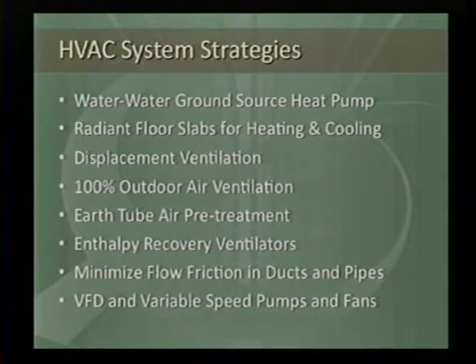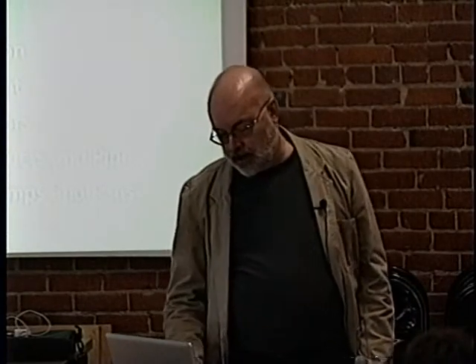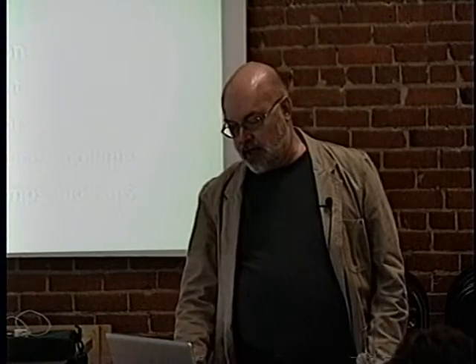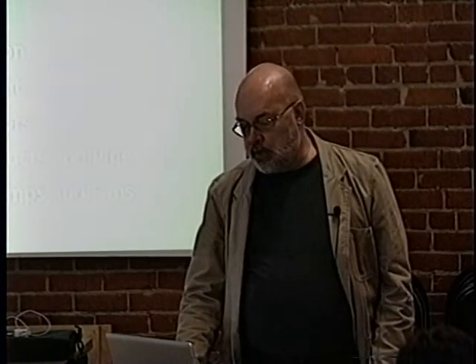We use displacement ventilation. We basically have 100% outdoor air ventilation, and yet our CFM requirement per square foot is about 20% of what a typical building with a VAV system would be. So it's a large reduction in that area. We used earth tubes for air pretreatment. That is, air goes into basically sewer pipe underground and then comes into the air handling unit. And we also do use enthalpy recovery ventilators. We did as much as we could to minimize the flow friction and maximize the efficiency of pumps and fans.